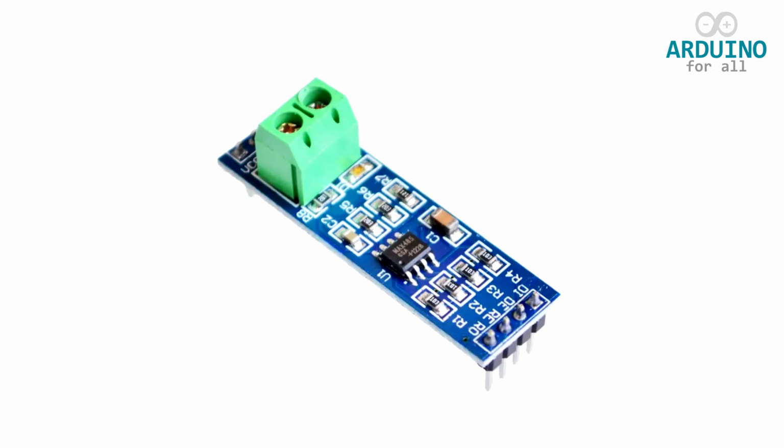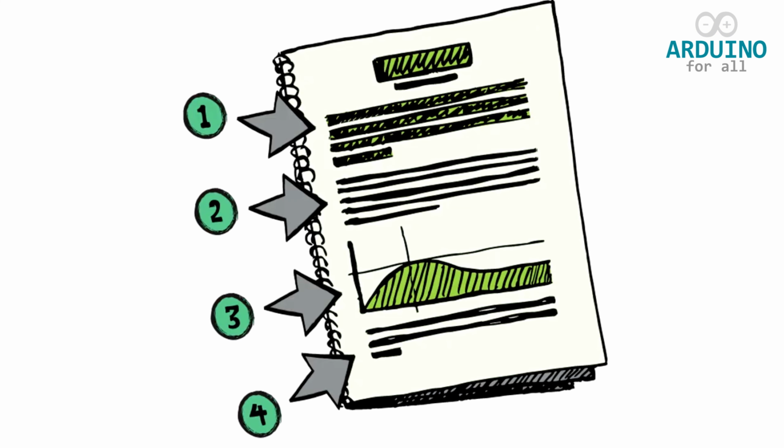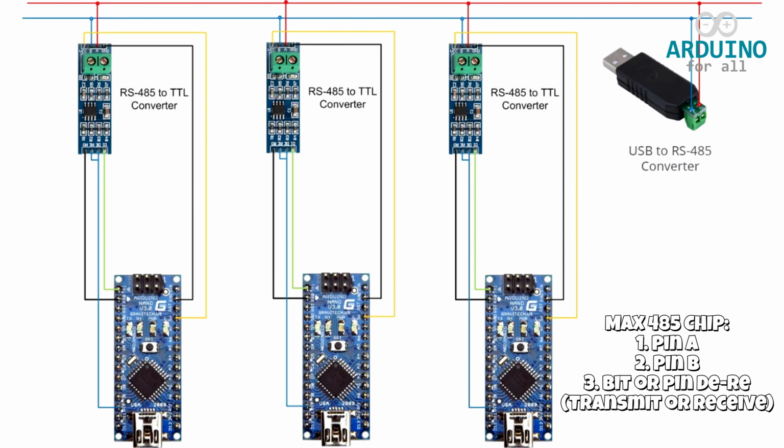These are not protocols, but electrical standards located in the physical layer of the OSI model. The most common is RS-485. It uses 5 volts, is differential, multi-point, and balanced, with 2 wires and a 120 ohm resistor. It supports up to 256 stations on a bus up to 1,200 meters long.